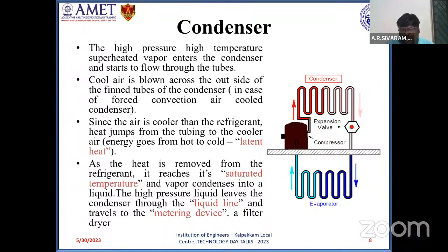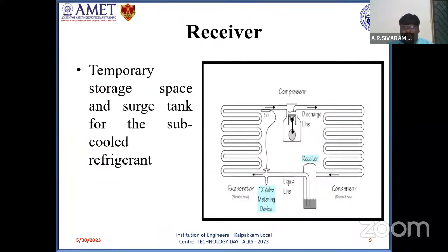So the high pressure liquid refrigerant leaves the condenser and enters a receiver tank. The receiver tank, which follows the condenser, is nothing but a temporary storage tank for storing liquid refrigerant. It receives the liquid refrigerant temporarily from the condenser, and then it transports it to the metering device.